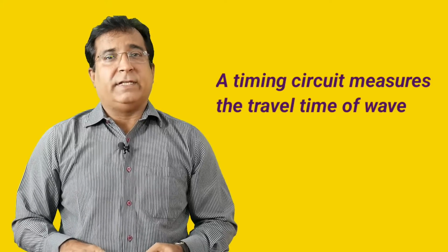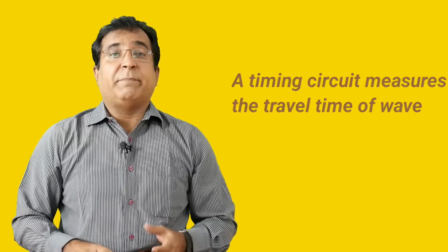Both techniques emit waves that travel at a known and fixed speed to the intended target material, where they bounce off the target and return to the sensor. Using the amount of time it takes for a wave to return to the sensor, the distance between the sensor and the material being measured is calculated. A timing circuit is incorporated in the system which measures the time of flight. This is the basic principle of operation behind any non-contact level measurement. Okay, but it's yet not clear what to choose.